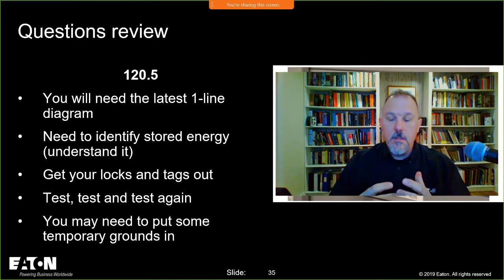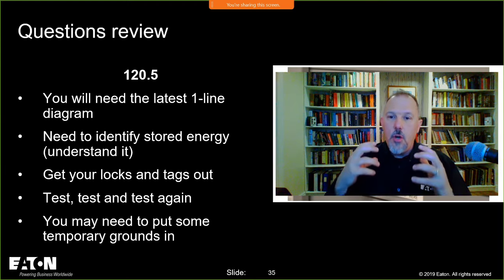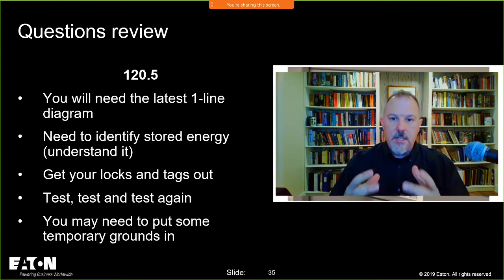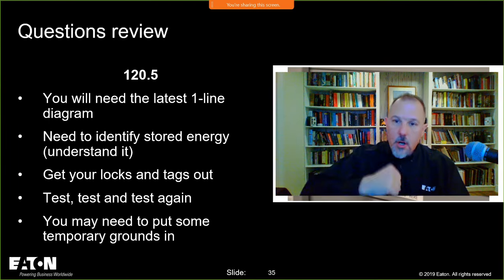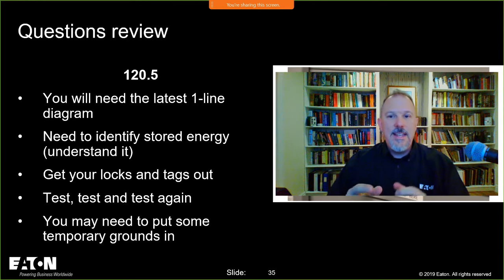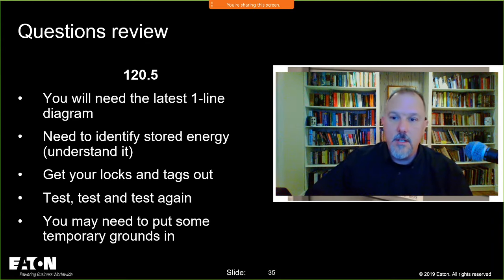That is an important thing: if you opened a power circuit breaker or an insulated case circuit breaker and you charged the handle but didn't close it, it has stored energy. Somebody presses that button, they can close that breaker. So let's watch this, and I'm going to quit talking.